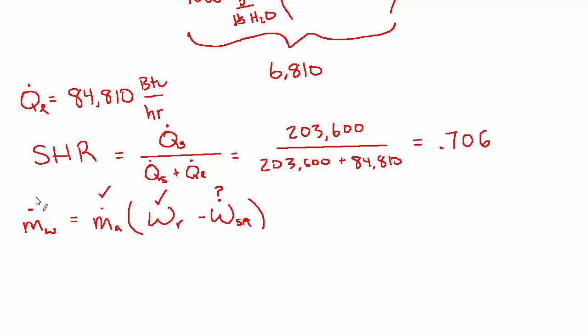And we know the total latent load. We don't actually know the mass flow rate of water, but we know the total latent load in BTUs per hour. So by the same principles we used before to figure out how many BTUs per hour were associated with those grains of moisture that were being added per unit time, we can go back in the other direction quite easily and say, okay, we have this much latent load—what's the mass of water that's being created in the space that's associated with that latent load? And we can plug that in here. So we have a bit of work to do here but it's quite doable. What's going to go into this spot should have units of either pounds of water per unit time or grains per unit time. So I'm going to do it in grains per hour, which means that these numbers for humidity ratio should come out in grains per pound.